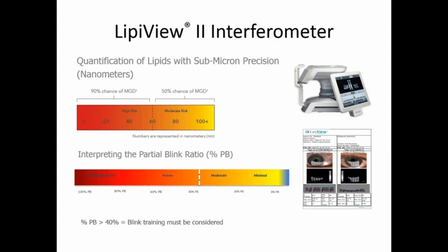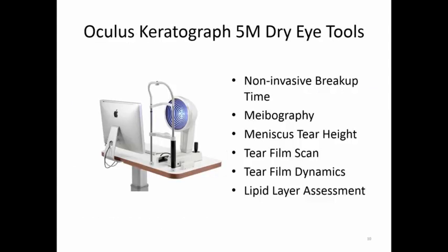Patients will then be brought into a dry eye testing room for us, and we have LipiView and LipiFlow technology. We've had it for well over probably about 1.5 years, almost from the beginning of our practice, which is relatively new. In fact, we just had our second anniversary or our birthday. LipiView 2 actually has an interferometer, but we still have the original LipiView, and we use that for measuring. Oh, I'm sorry, a Meibography, I should say. But we use the LipiView for measuring lipid layer thickness as well as for assessing blink dynamics, how frequently the patients blink and how complete the blinks are.